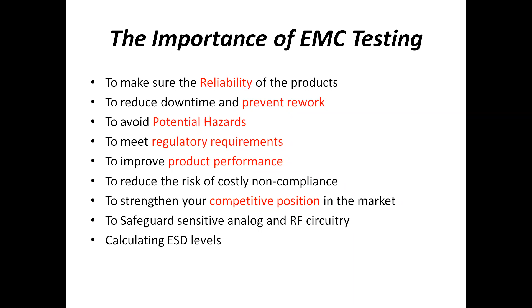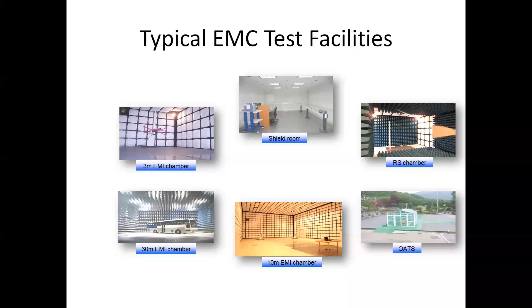These are some of the test laboratory facilities available: 3-meter EMI chamber, 30-meter EMI chamber, and 10-meter EMI chamber. Depending upon the product size, we can utilize any of the chambers. And shielding room, RS chamber, that is radiated susceptibility chamber, and OATS, open air test site facility. This open air test site facility is commonly set up in hilly areas where there is no other radio frequency communication interference, or any other signal spectrum available in the area. Also, depending upon your product implementation side, we can choose the chamber.